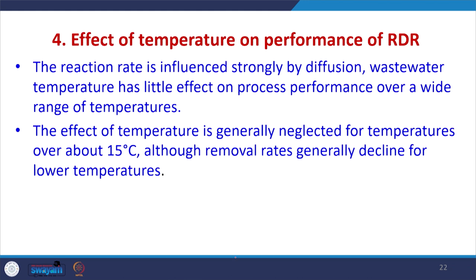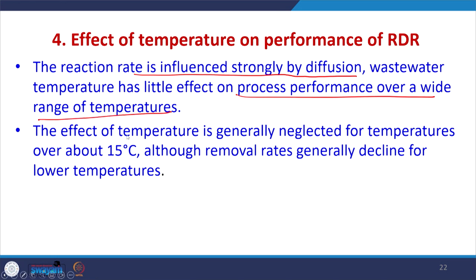Effect of temperature: as with other types of biological wastewater treatment systems, temperature affects the performance of RDR. The reaction rate is influenced strongly by diffusion, so wastewater temperature has little effect on process performance over a wide range of temperatures. The effect of temperature is generally neglected for temperatures above 15°C, but below 15°C it will certainly decrease the performance of RDRs.